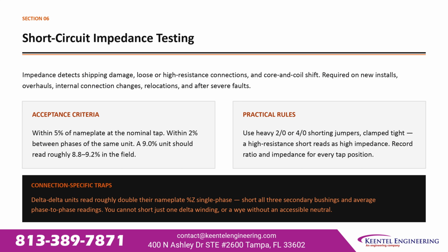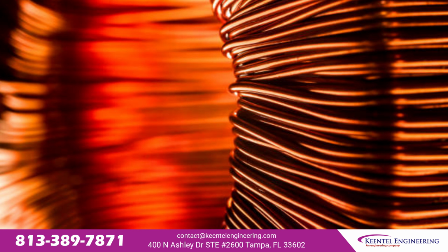Record ratio and impedance for every tap position, and watch for connection-specific traps. Delta-delta units read roughly double their nameplate percent impedance on a single-phase test. Short all 3 secondary bushings and average the phase-to-phase readings. You cannot short just one delta winding or a Y winding without an accessible neutral.